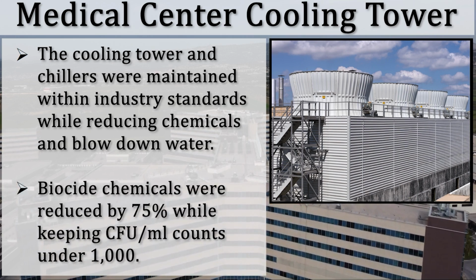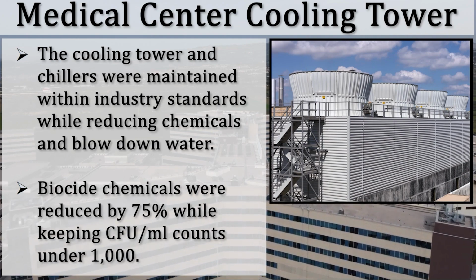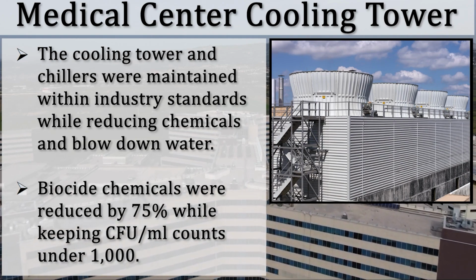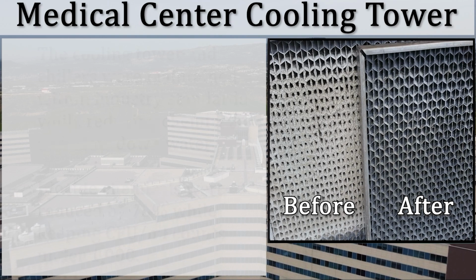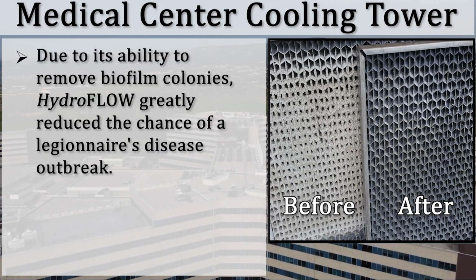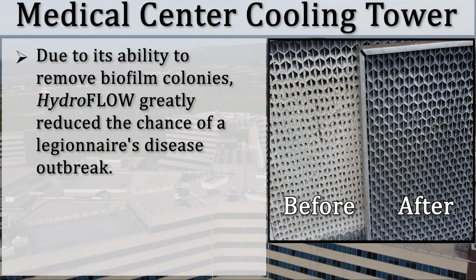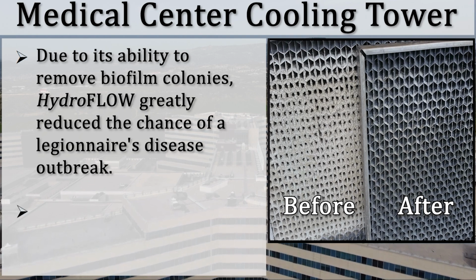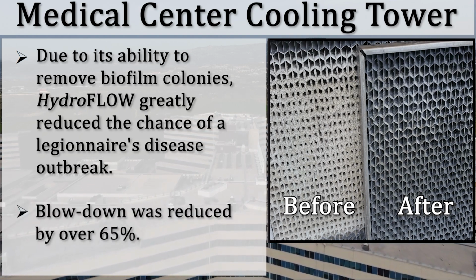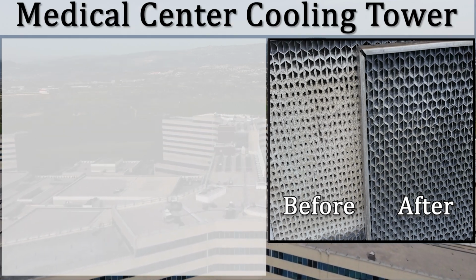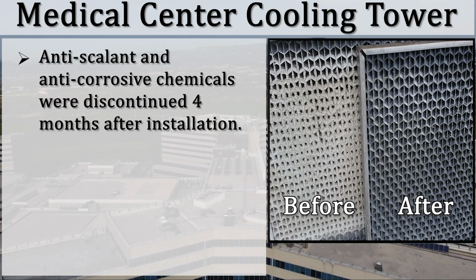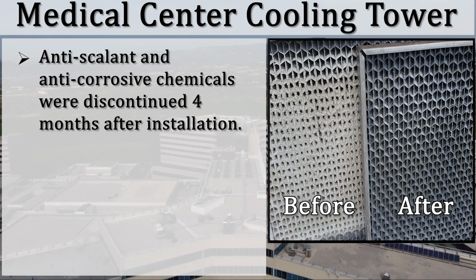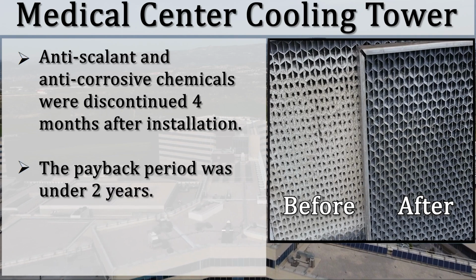Biocide chemicals reduced by 75% while keeping CFU per milliliter counts under 1,000. Due to its ability to remove biofilm colonies, HydroFLOW greatly reduced the chance of a Legionnaire's disease outbreak. Blowdown was reduced by over 65%. Anti-scalant and anti-corrosive chemicals were discontinued 4 months after installation. The payback period was under 2 years.